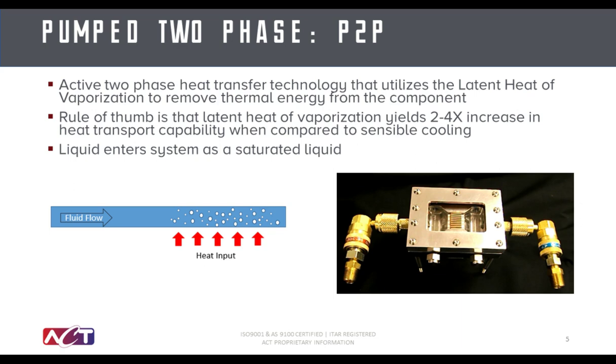The difference between a glycol system and a pump two-phase system is that the water enters the system at a saturated condition, meaning it's close to its boiling point. As it flows through the heated component, it picks up that energy and boils the fluid, transitioning the liquid to its vapor state. The vapor then travels on to another part of the system where it is condensed, gives off its latent heat, and the cycle repeats.